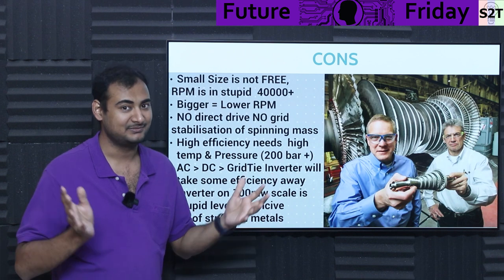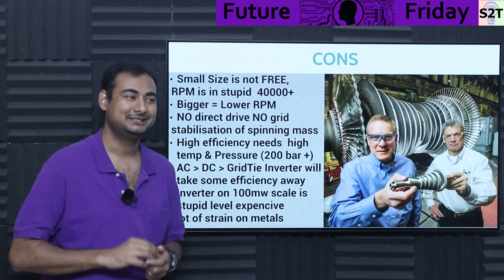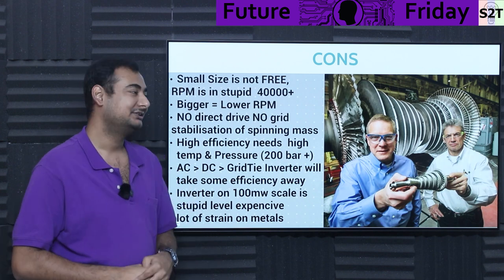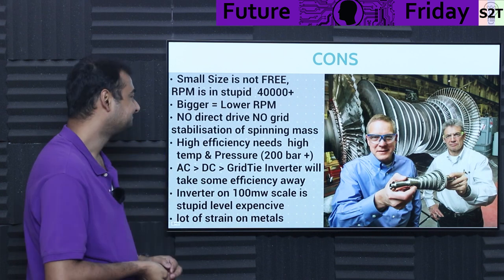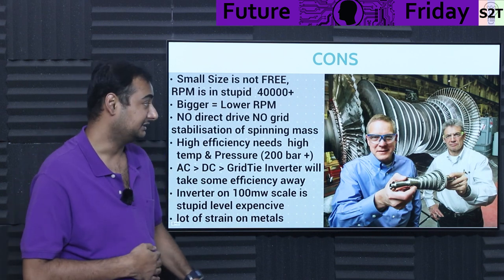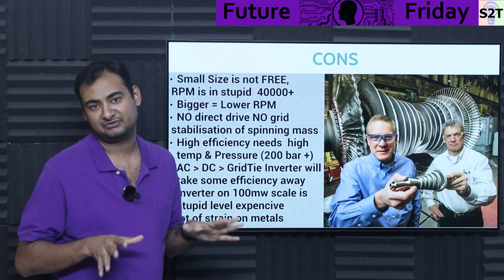And again, even ceramic bearings will not work at that point in time. You have to have ceramically cooled bearings, meaning you have to send oil to it to cool it. So that's above around 20,000 RPM. At that point, you might look into magnetic bearings. So the RPM on this puppy is very high. Now, the steam turbine systems are designed for very low RPMs, around 1500 RPM.